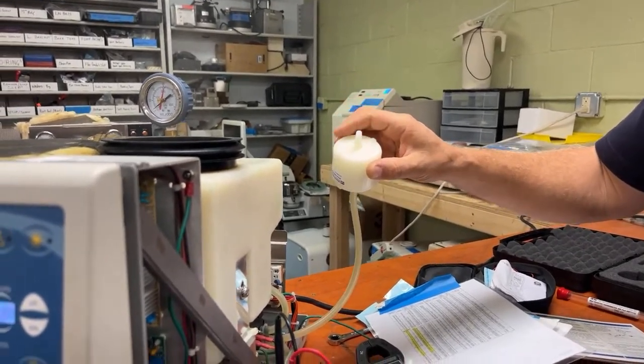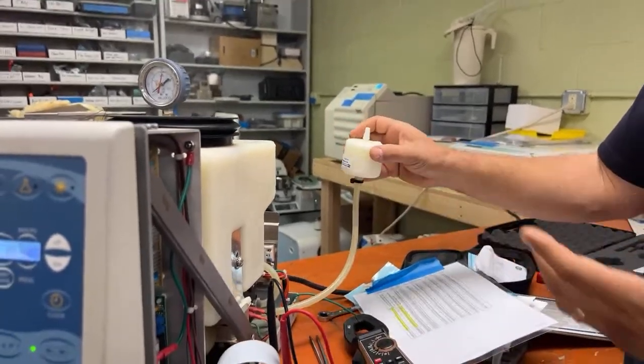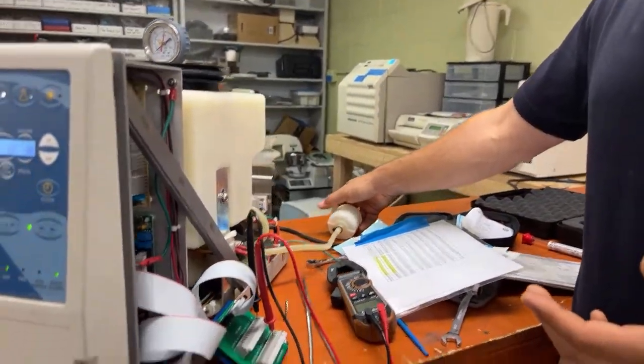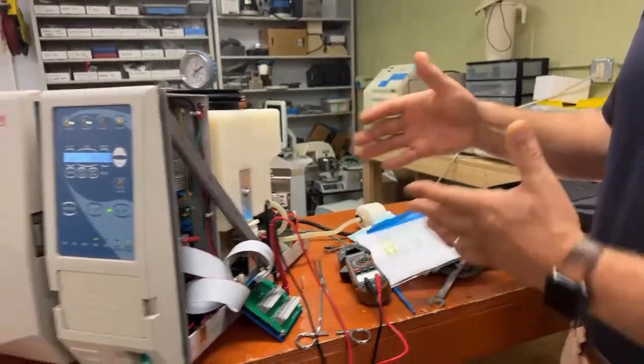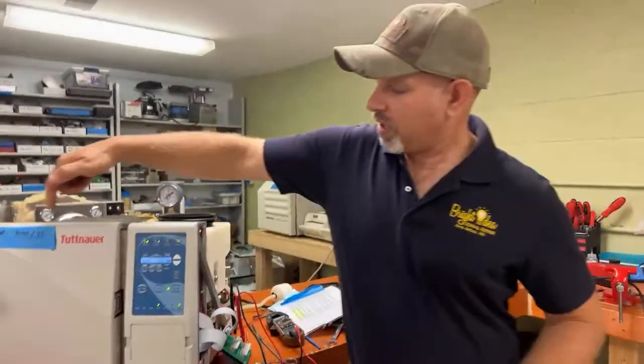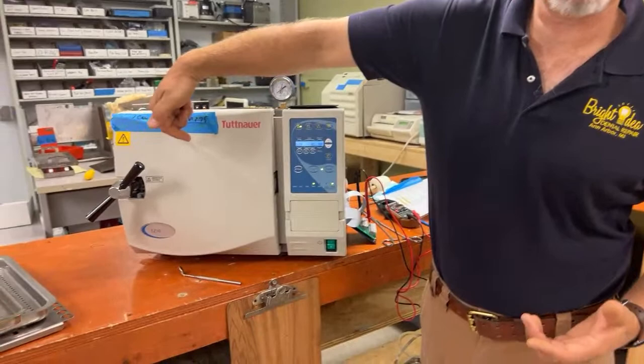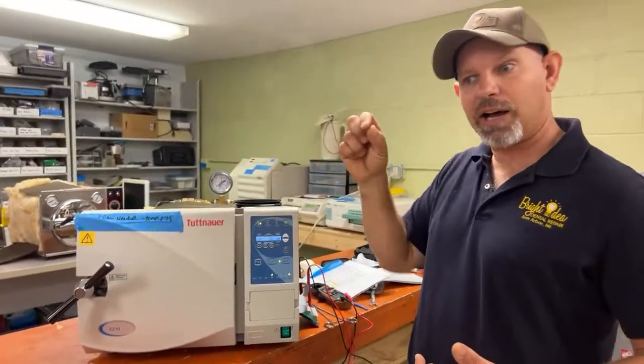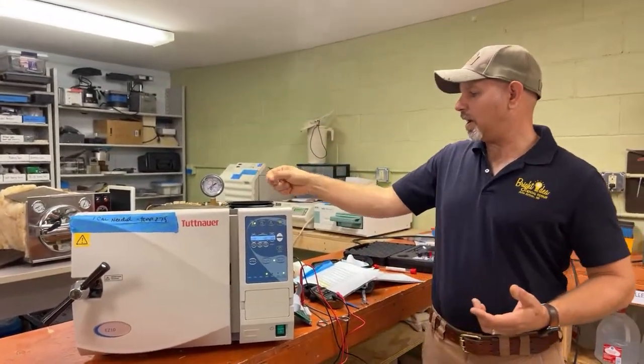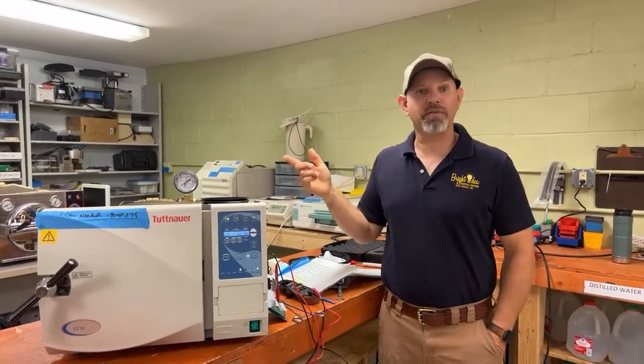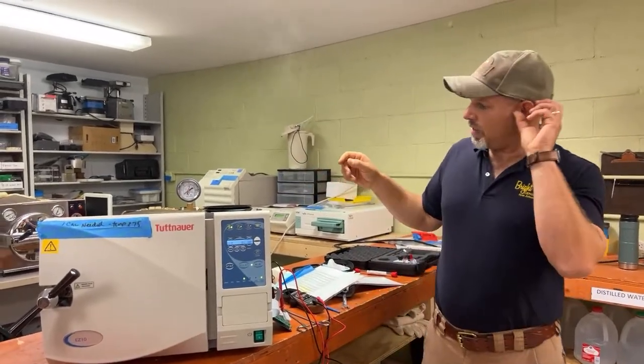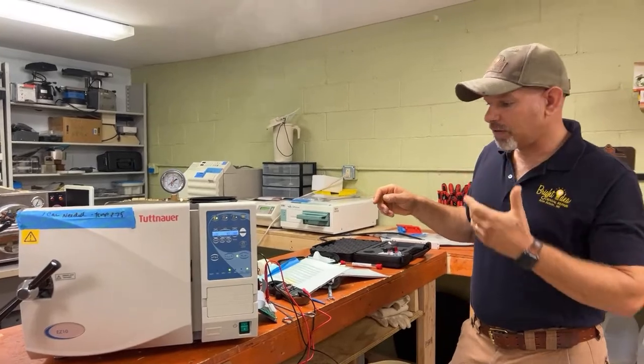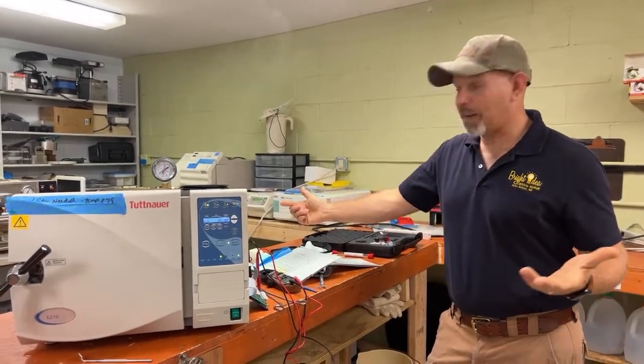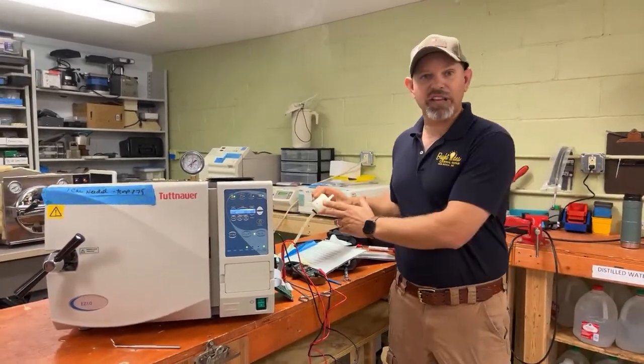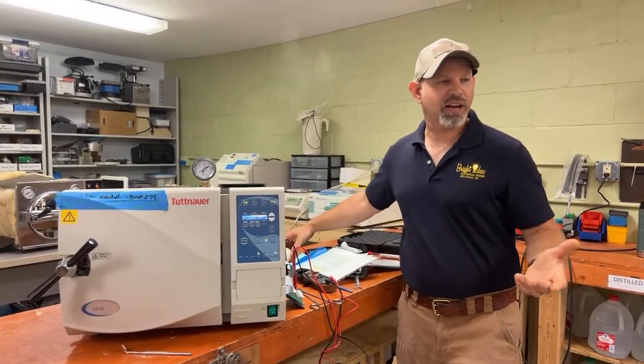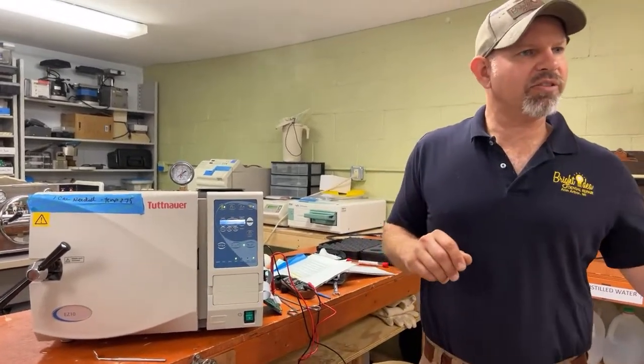All right, and this should be replaced about once a year, because the preventive maintenance on these autoclaves includes the door gasket, the bellows, the little silver air jet valve, and then the HEPA filter. So again, these are also RPI kits. Can you get one of those RPI kits?